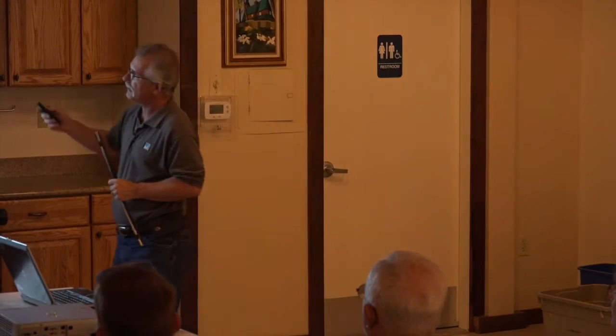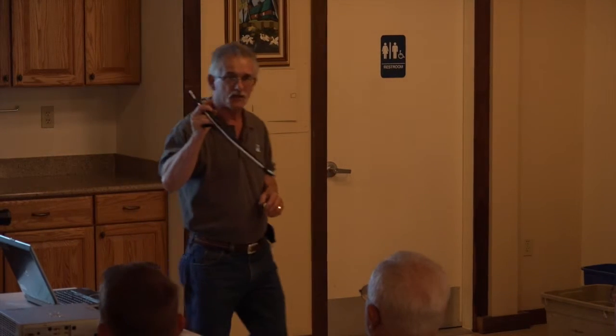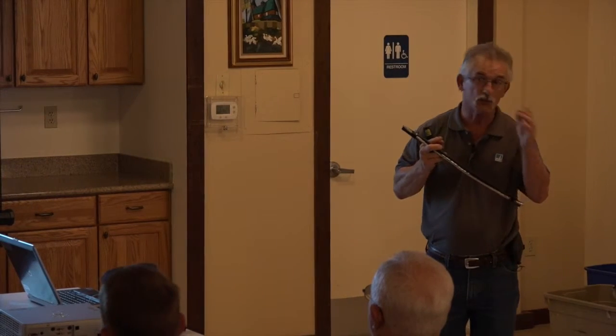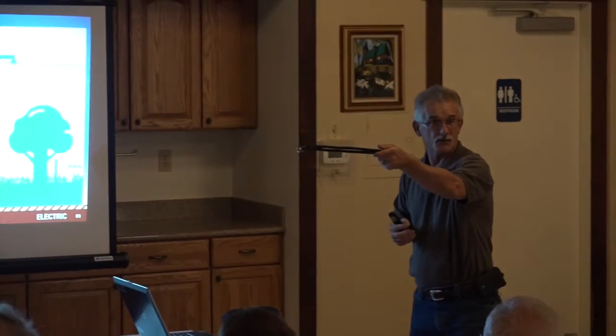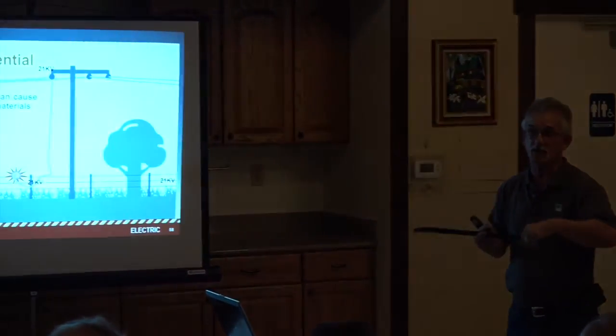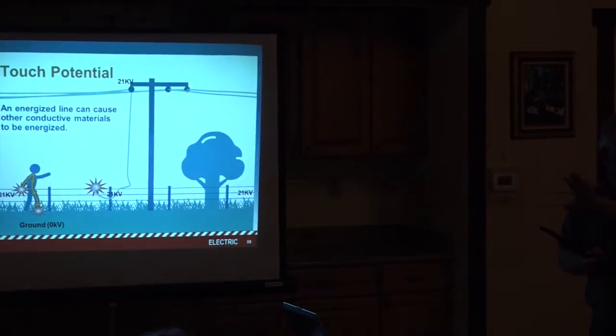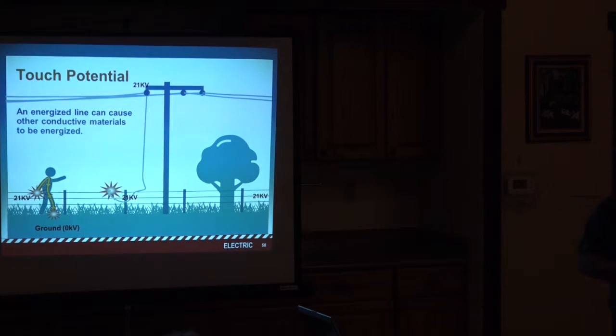This is called touch potential. It means that when our wire comes down, anything that wire touches can potentially be energized. So you need to be cautious - you may have a wire down over on the fence around the pool, and you may think you're far enough away, but the reality is that entire fence can be energized with 21,000 volts from the neighborhood wire area.